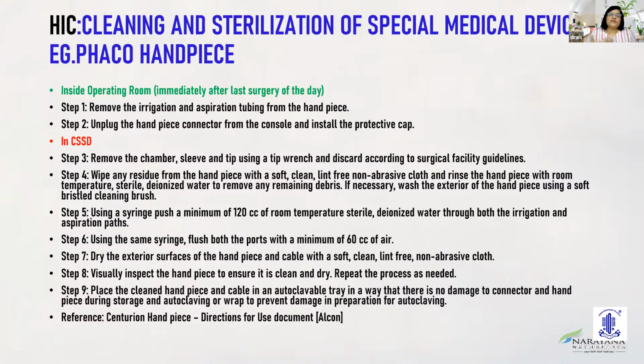So we have protocols for this also, for how you will handle the special medical devices. For example, a phaco handpiece: in the operating room, you will remove the irrigation aspiration tubing from the handpiece and unplug the handpiece. Then in CSSD, you will remove the chamber sleeve and tip using a tip wrench and discard according to surgical facility guidelines.